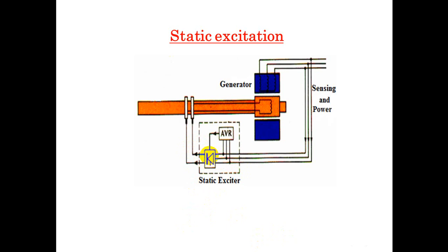Clearly, they cannot be mounted in the middle of the shaft, and in practice are mounted on a rotating wheel on the extreme end of the shaft at the exciter end. This makes them easily accessible for inspection, testing, or replacement.